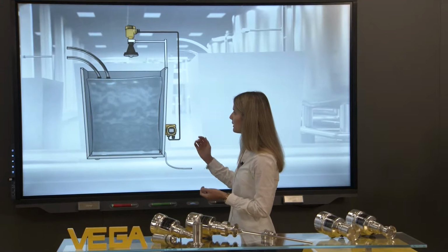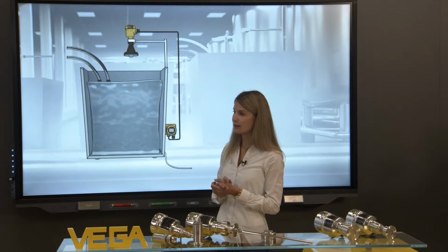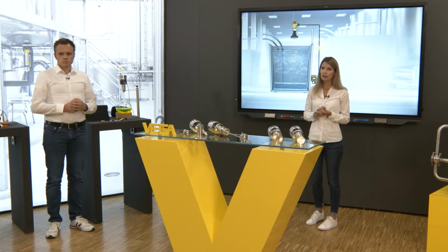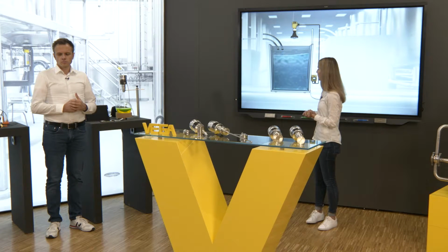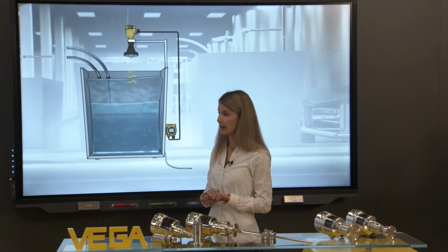Also here we use the VEGAPULS 64. We also measure through the bag, similar to what Florian just showed us in the glass bowl. It's not glass, but in that case it's a polymer bag. But it works in the same way, even if there are wrinkles inside during the expansion of the bag, and even if there's condensate. So really clever solution, not only with glass, but also on the polymer bag.